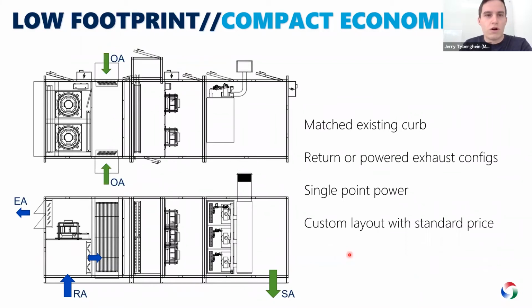Moving on to another example of that compact economizer. We did about 7 of these recently, and we're building 8 more right now. This is more of a custom layout and a more all-in-one type system. So it's this compact economizer. This specific example has a powered exhaust fan. We can do powered exhaust or return. So you have return air that comes in here and exhausts out here, or it can recirculate into the supply airstream.